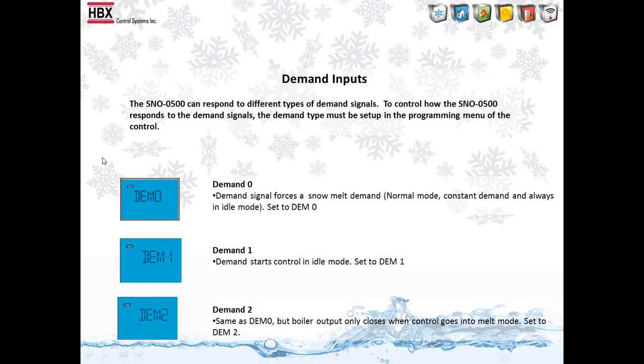So in some instances you might have somebody set the snow intensity to 50 or 60%, so they don't mind shoveling their snow off their driveway once in a while. So it'll accumulate on there up to 50 or 60%. But if they actually don't want to go out and shovel the snow, they can have a push button on there where they basically push the button and it'll go into force melt. So it'll instantly go into melt mode.